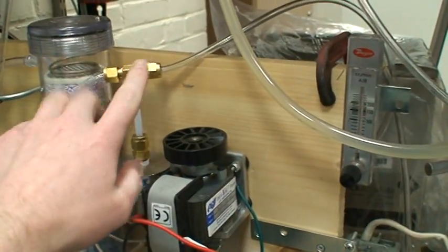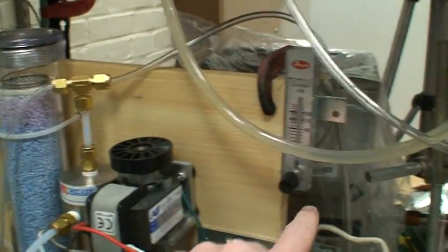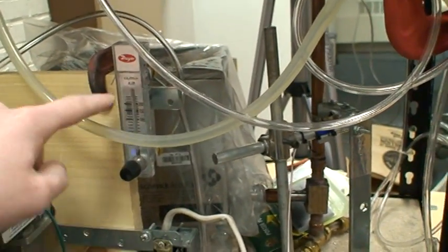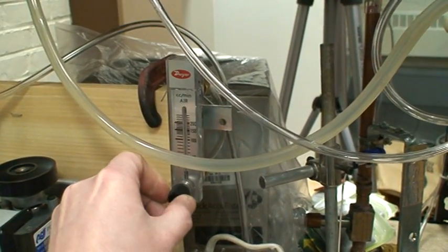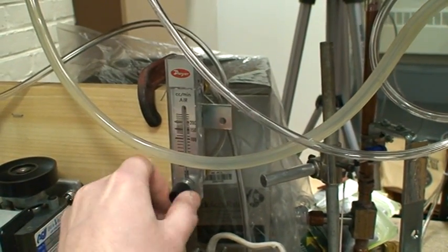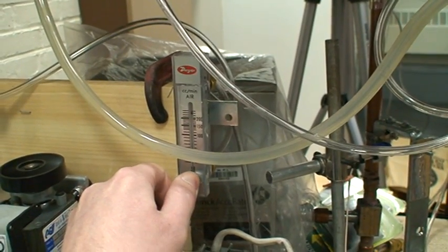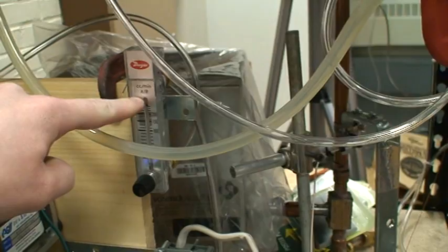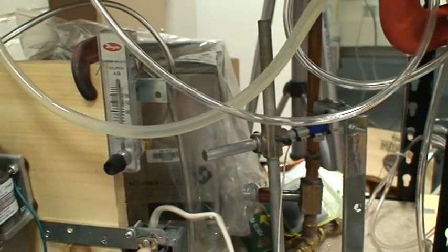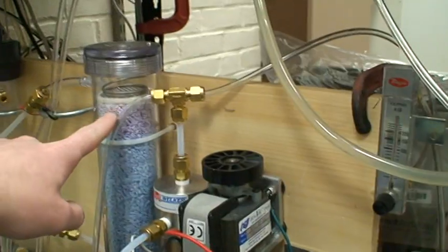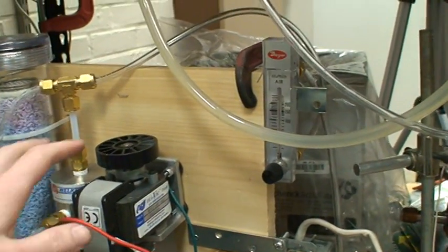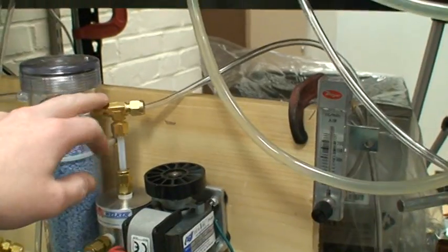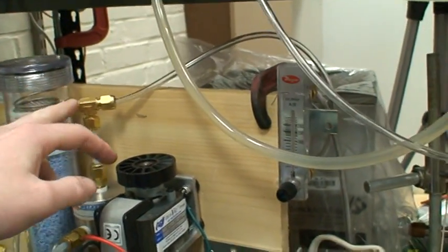And then we have the line splits. So this one goes to a flow meter or rotameter, and so when it's running, we're going to sample at 1/4 liter a minute. So you have to set this each time so that you're getting the right amount of flow. You want 250 cc's per minute, so you want the volume to be right about here. I'll turn this off because it's loud. And the excess is vented back into the hood. So this line goes back into the hood return. And the reason you do that is because if you don't vent the excess, you get a pressure buildup in the line, and then it takes forever for the sensor to respond.